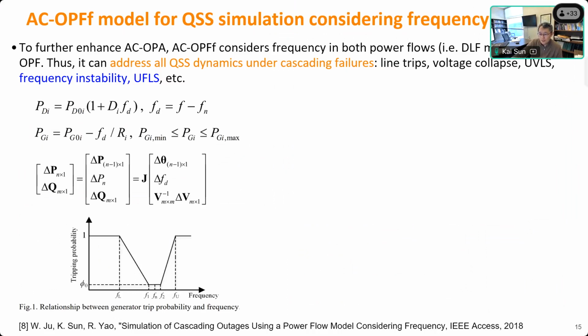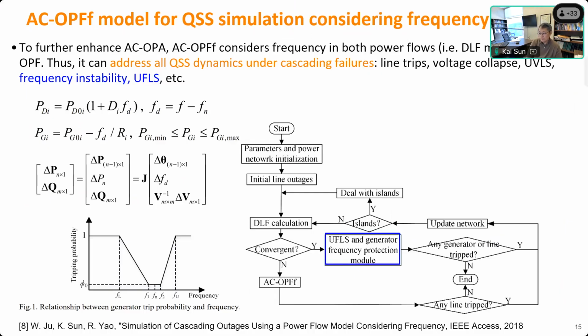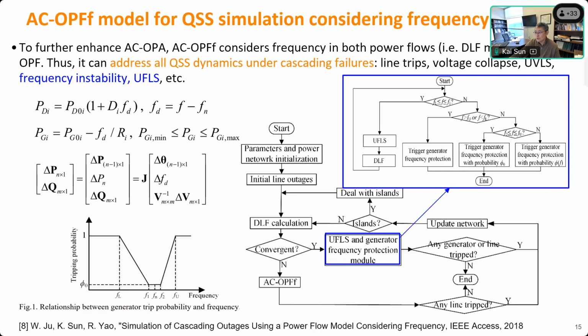And you can design the generator trip strategies based on the frequency deviation. If the frequency is too high, there will be over frequency protection. If it's too low, there will be under frequency protection. You can design such a strategy based on the NERC standard or some industry practice. Then you can do the simulation. So this is the improved OPA model, adding the frequency function into this model. You can integrate the under frequency load shedding and generator frequency protection. For instance, you can compare frequency to the different thresholds and decide which generator to be tripped.